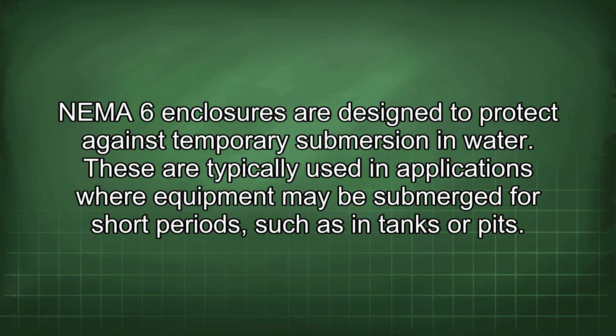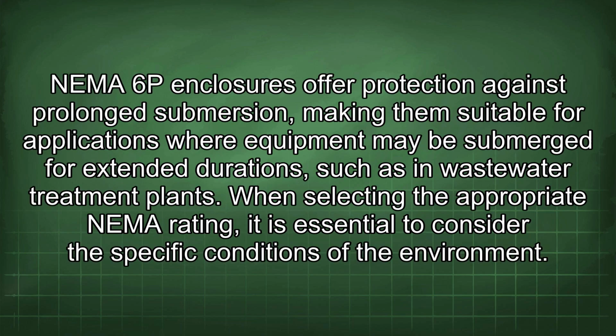NEMA 6 enclosures are designed to protect against temporary submersion in water. These are typically used in applications where equipment may be submerged for short periods, such as in tanks or pits. NEMA 6P enclosures offer protection against prolonged submersion, making them suitable for applications where equipment may be submerged for extended durations, such as in wastewater treatment plants.